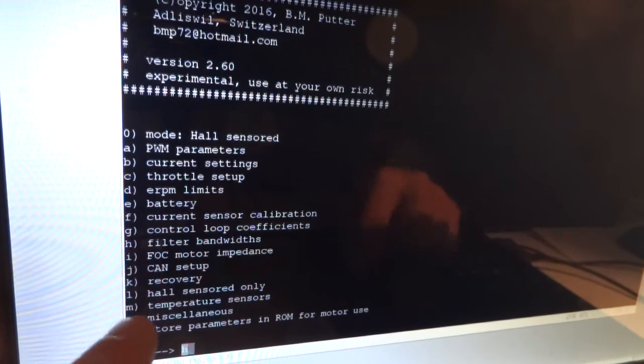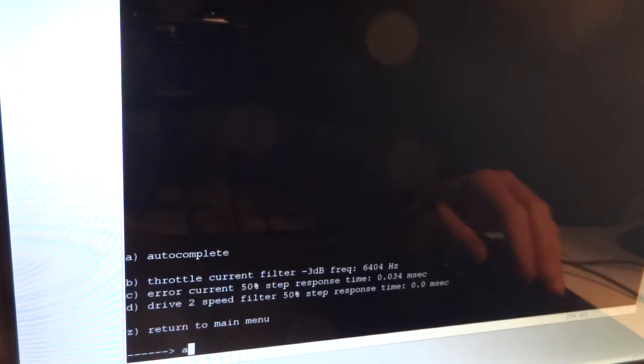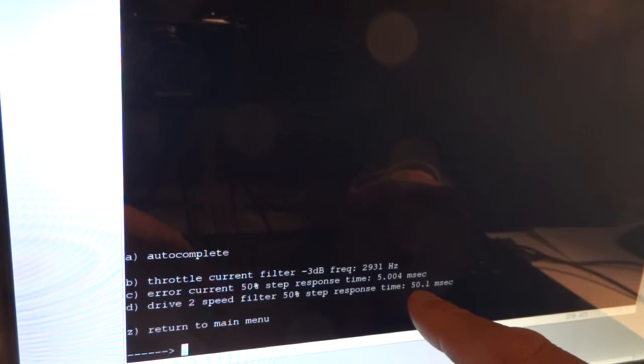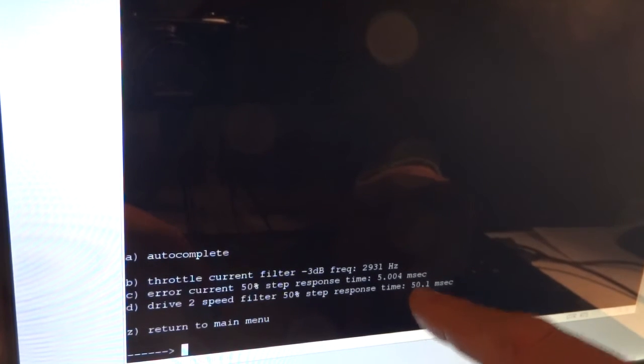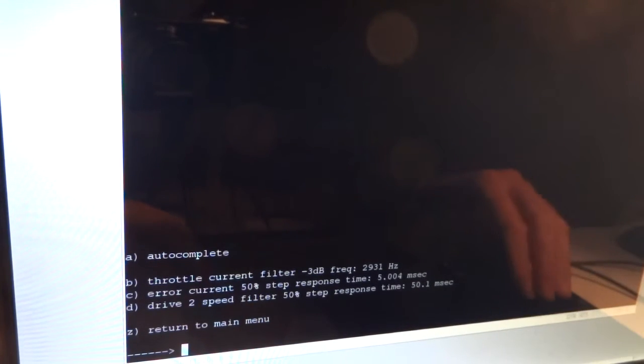Okay, filter bandwidth is just an autocomplete. The change with the previous version is now the speed filtering in drive 2 is dependent on the mode. It's 200 millisecond autocomplete for sensorless and 50 for Hall. It spools up quicker if you use 50.